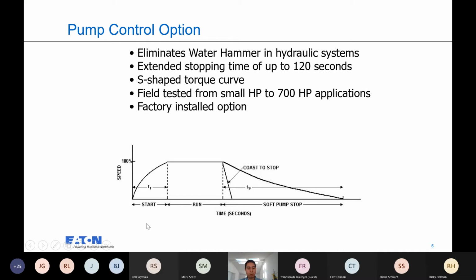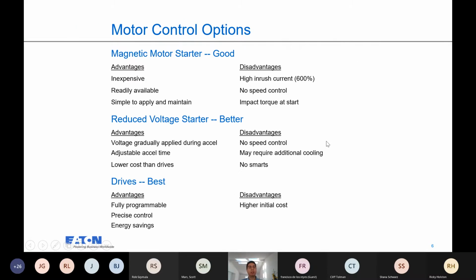When we go through the soft start to coasting to stopping, we can also use VFDs or soft start to reduce the water hammer, by extending your stop time, using dynamic braking, and also helping protect your mechanical motor applications. Here are some basics. Here are the advantages of across the line starters: inexpensive and readily available. Then you go to your better and your best options, which are reduced voltage starting and variable speed control, which we will discuss, and how we can take advantage of it by changing the speed.